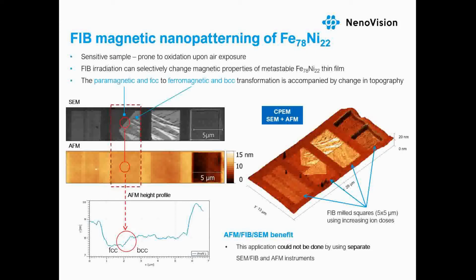In this case, the step between high and low magnetic moment was 470 picometers high, as depicted in the height profile. For better data interpretation, the CPEM view was used to merge the topography and material contrast. Additionally, this alloy represents a sensitive sample prone to immediate oxidation, and for that reason, this application could not be done by using separate AFM and FIB-SEM instruments.